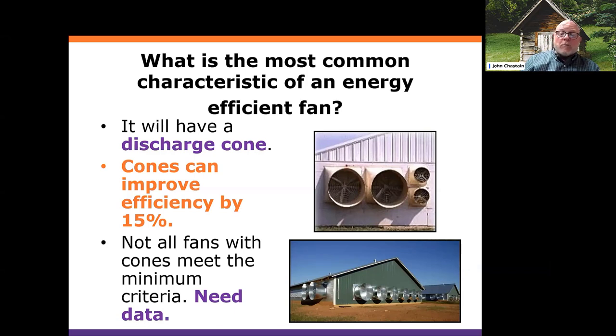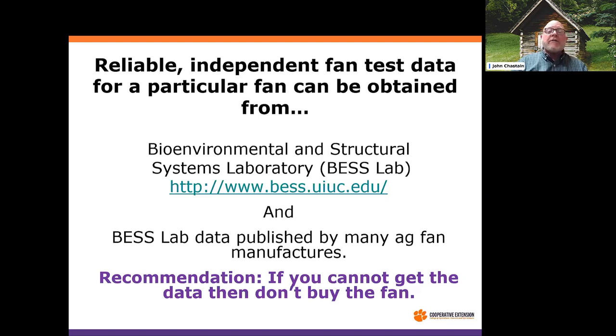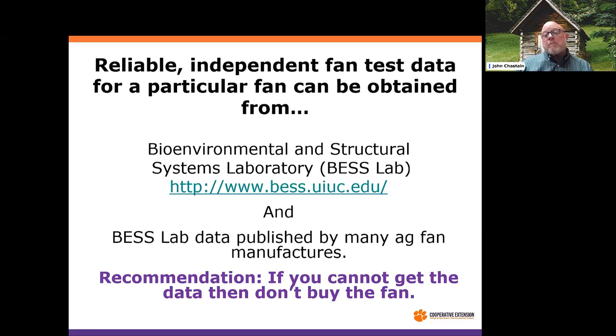We've got to have actual data on the fan we want to use, because good data will show us all of these things. Where can you get this data? We mentioned BESS Lab — they have a website where they report information. Manufacturers pay to have their equipment tested using standard methods. Honestly, I just Google 'BESS Lab' and it's typically the first hit. Many major manufacturers also publish that data in their literature with the associated BESS Lab test number. But here's the bottom line: if you don't have the data, don't buy the fan.